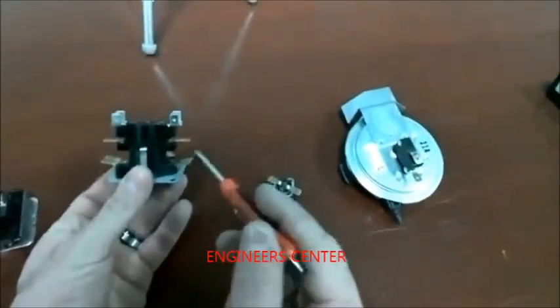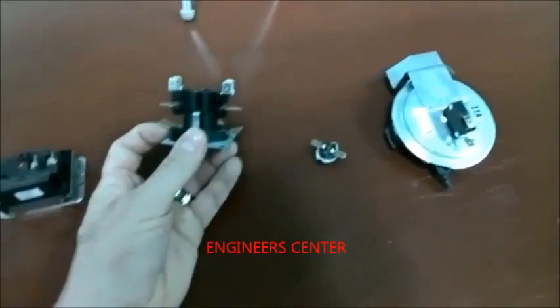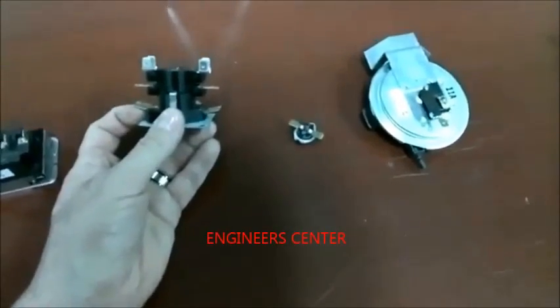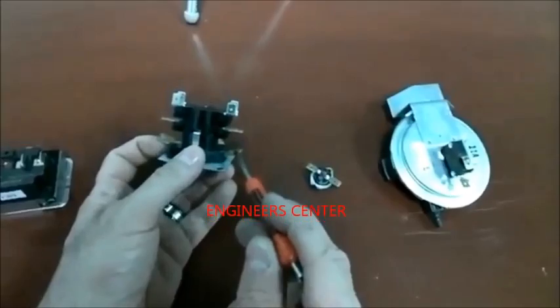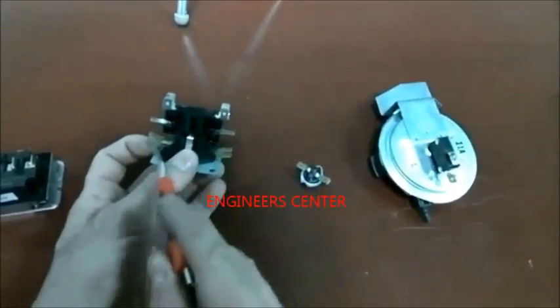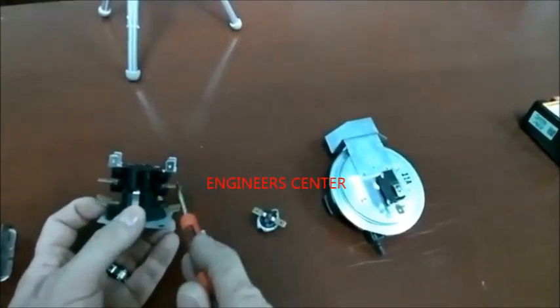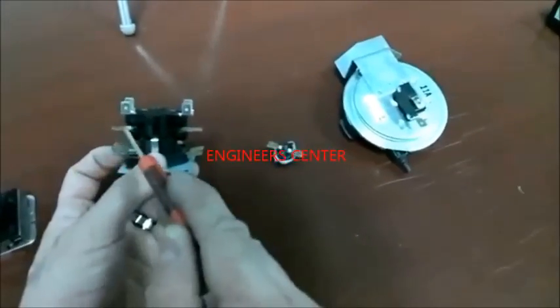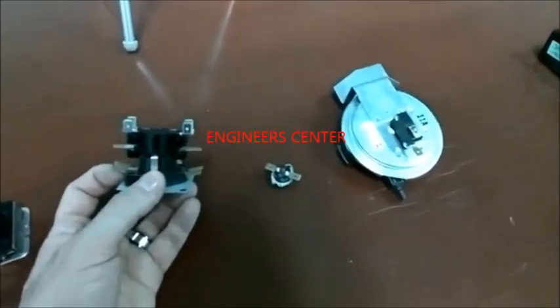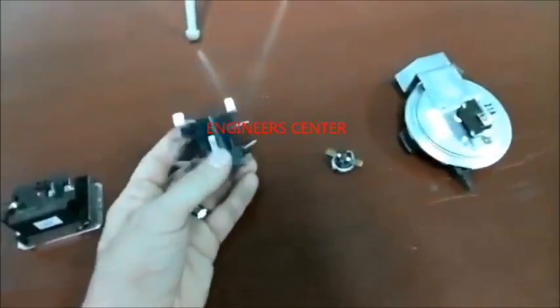The purpose would be, maybe if you were working on a straight cool with strips unit, and you wanted the heat to come on, you would send common to one side, and you have the energized from white, and you would send power here and here, and this one would then bring on your heat strips, and then this one would bring on your blower motor. So your heat strips would come on, and then just seconds later your blower motor would come on after giving them a chance to warm up. That's what that's generally used for.